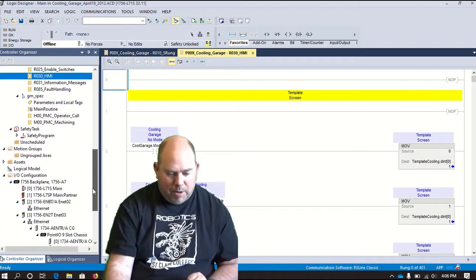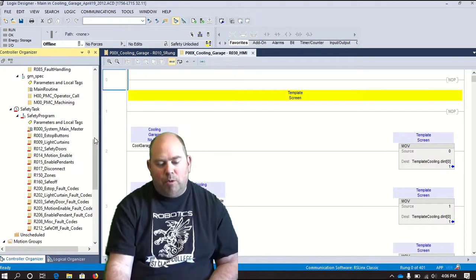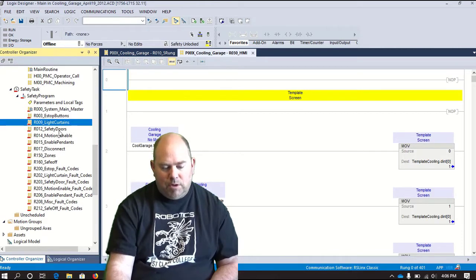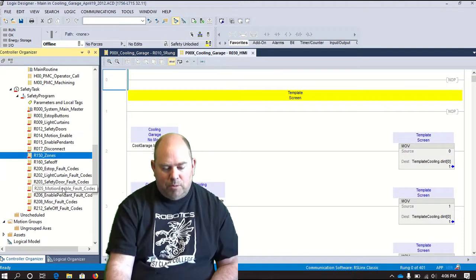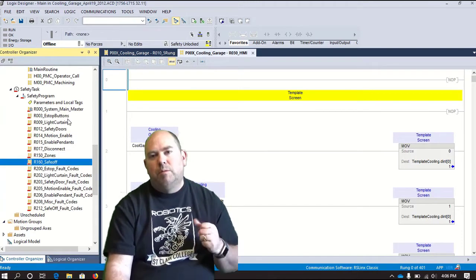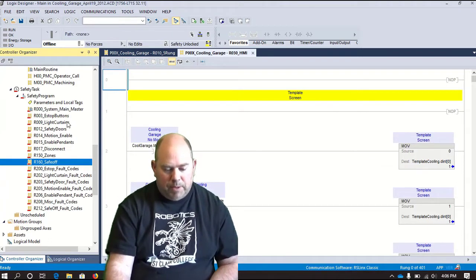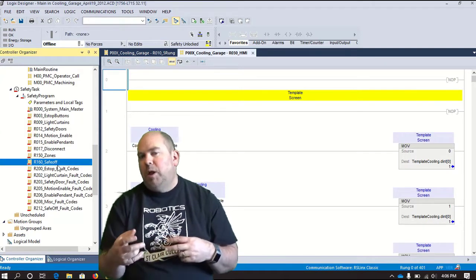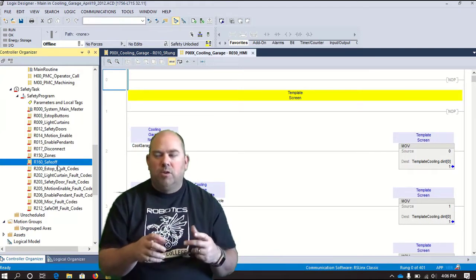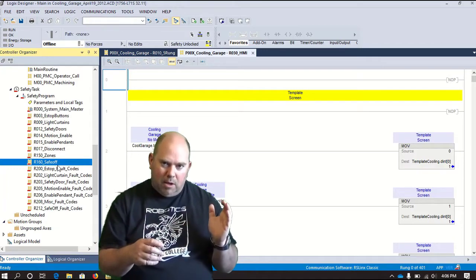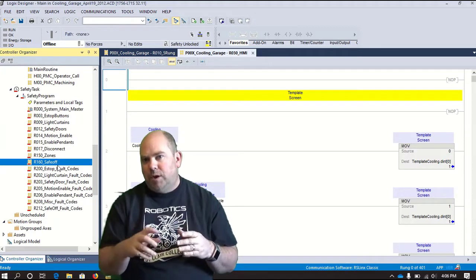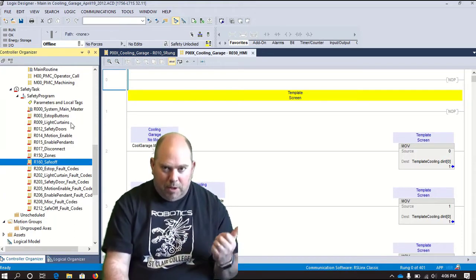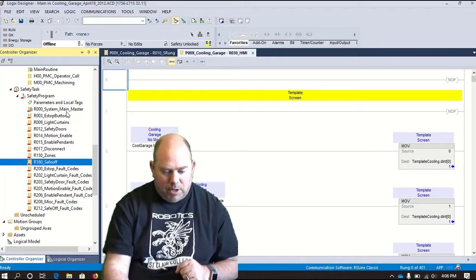So then on top of that we have our safety program. Now this is going to look pretty familiar to what you've seen. So we've got e-stops, light curtains, safety doors. And then we've got some zones. And then this safe off is actually the output so we control. So let's look at some of the blocks that are being used in here. The rest of everything down here is just getting fault codes out of those blocks so we can display them on the HMI. That's one of the things with these blocks. You can actually get the fault codes out of them. So if you lose channel A on a block you can actually get a fault that says channel A fault. But you need to do a lot of coding to be able to get those things out.